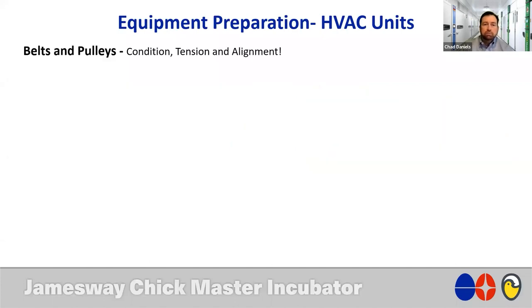When I talk about belts and pulleys, I talk about condition, tension, and alignment. So if I have that big seasonal adjustment, it's usually pretty convenient to make sure that I've got enough belts on hand. I look at that as an opportunity to maybe change those belts and get prepared for the season. Anyway, we talk about condition. We want to try to avoid dry and cracked belts.